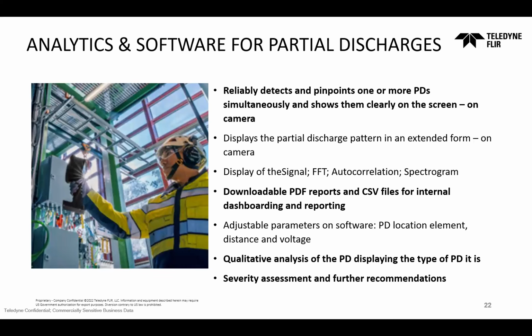And then is when you can say, okay, here we got a partial discharge. The camera is discriminating all the non-relevant sound, but always apply common sense for this use. You have the pinpointing and the pattern, and then you can say this is a partial discharge. This displays in the cloud the signal, the FFT, the autocorrelation, the spectrogram. This is something that you can actually provide to acoustics experts if customers have some.